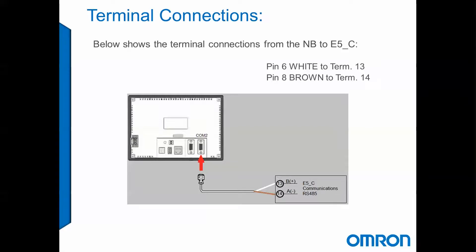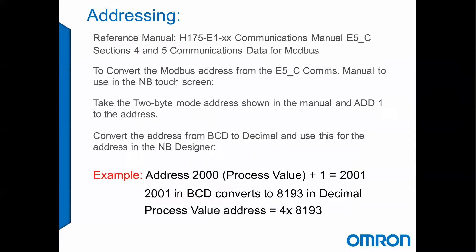We're going to be using COM2 on the Touchscreen, so we're going to attach the DB9 to COM2. On the other end, pin 6, which was our white wire, is going to go to terminal 13 on the controller. Pin 8, which is the brown wire, is going to connect to terminal 14.